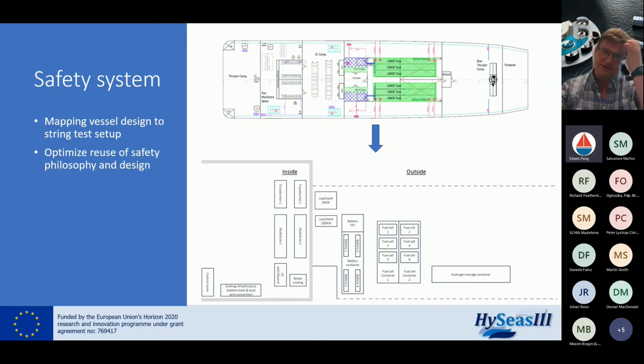When we started on the safety system and how we wanted the string test to be designed, we started by looking at the design for the vessel. This was not the vessel we ended up with, but it was the initial design, and we used it to map the string test to be as equal as possible for the safety view, which let us reuse a lot of the safety philosophy and design over towards the vessel at a later stage.